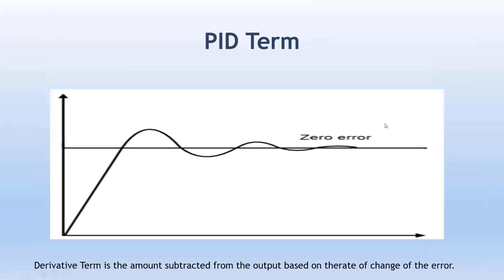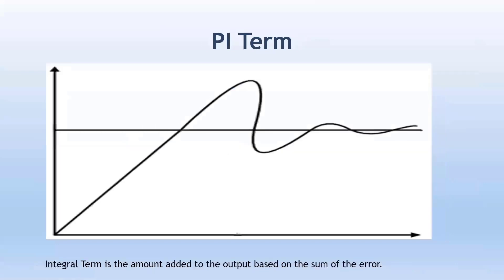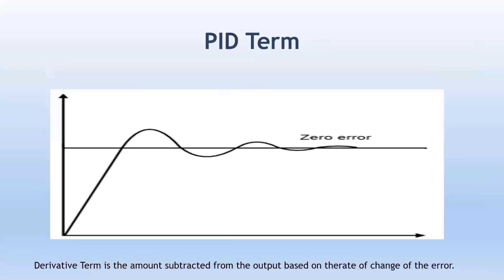There is no system in the market that has no disturbances — disturbance is always a factor in any control loop. To take care of disturbances, or the rate of change of error, you add a D term. The derivative term is the amount subtracted from the output based on the rate of change of error. Most PID loops can be tuned with just P and I terms, but there are some loops that actually need the D term as well.